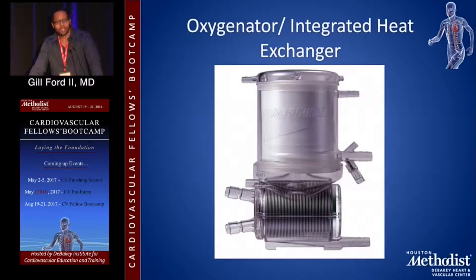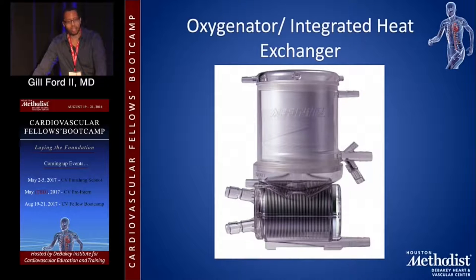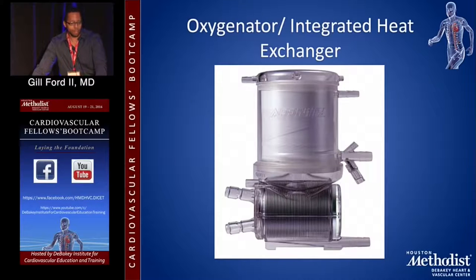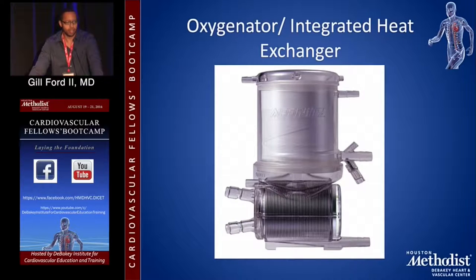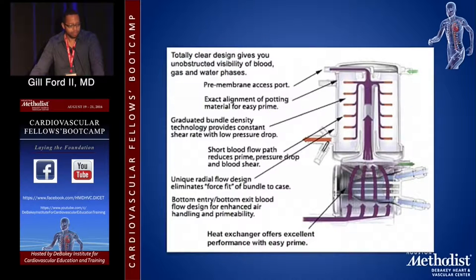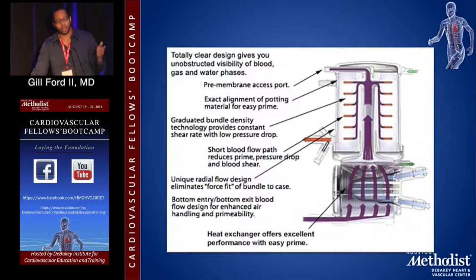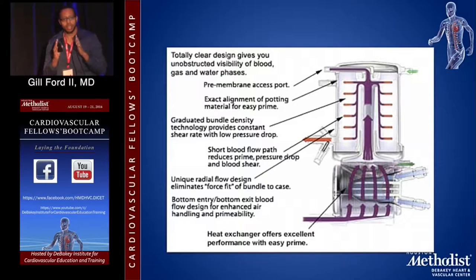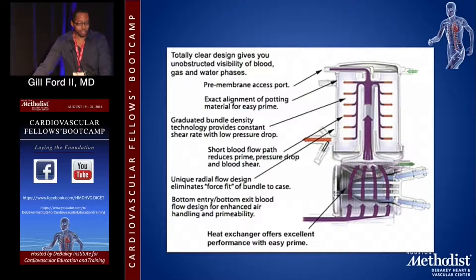Now, the oxygenator — this is the magic I was talking about at the beginning. Blood goes into your oxygenator through the heat exchanger at the bottom. All oxygenators usually come with an integrated heat exchanger; we hook up an external water bath to cool and warm the blood, reducing the patient's metabolic demand during the case. After the heat exchanger, blood goes through hollow fiber membranes in the top part, which is the oxygenator itself. That membrane separates the blood and gas.